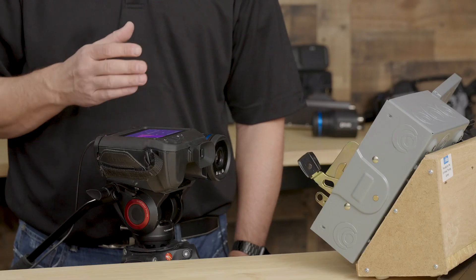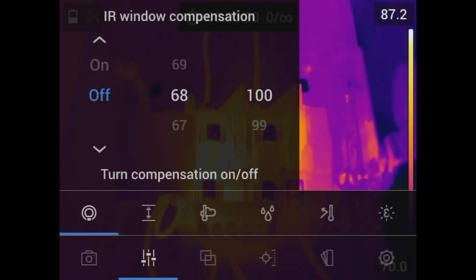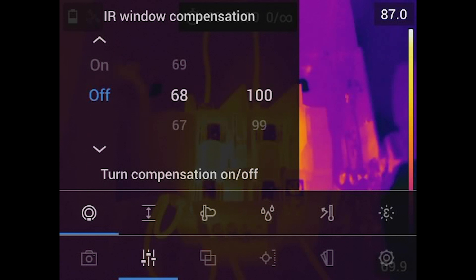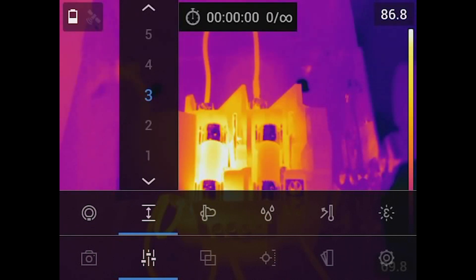Here in the settings, we can turn on compensation for looking through an IR window. For those of you who use IR windows to look inside your motor control center, MCC buckets, or panels, this allows you to compensate. You might want to compensate for temperature, but you also might want to compensate for the transmission of the window.